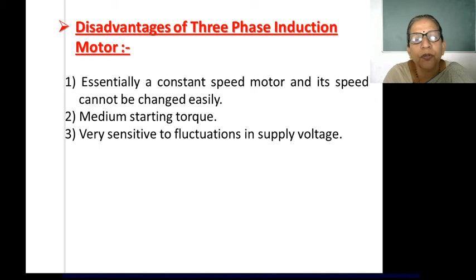Second drawback is that the motor provides a medium starting torque. Starting torque is not that high. Third disadvantage is that it is very sensitive to fluctuations in supply voltage. So whenever there is some variation in the supply voltage, it is going to affect the torque produced by the motor, because torque is proportional to voltage.